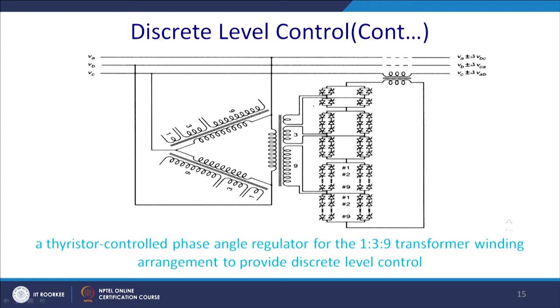So, in this configuration we can have the same thing, where voltage will be added in quadrature, that is BC, CA and AB with the phase voltage, and that will actually be the phase angle regulation. You will inject the voltage in quadrature. This is the thyristor control phase angle regulator for 1, 3, 9 transformer winding arrangement to provide discrete level control.